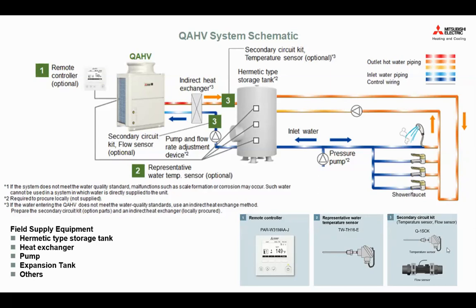And there are some field supply parts. So for example, a hermetic type of storage tank. Obviously the tank needs to be airtight, right, to store the water, and then you insulate it so it properly retains the heat. And because the QAHV doesn't come with a double wall heat exchanger, you will still need to have a double wall heat exchanger somewhere to make sure there's no contamination. Depending on where you are, some of the local requirements may be slightly different, but in general, I believe most jurisdictions in Canada will require a double wall heat exchanger for domestic hot water.